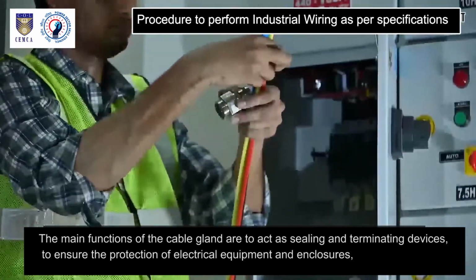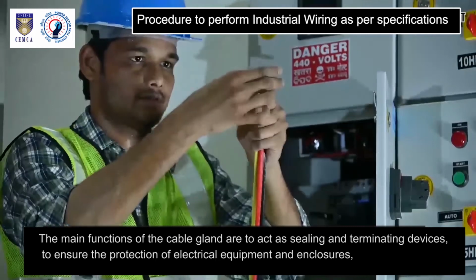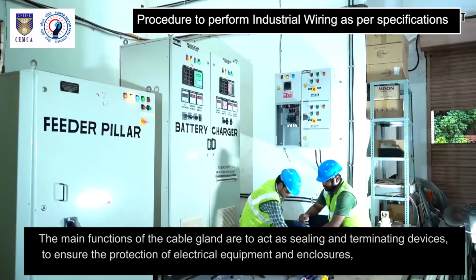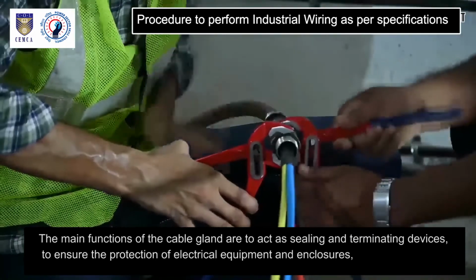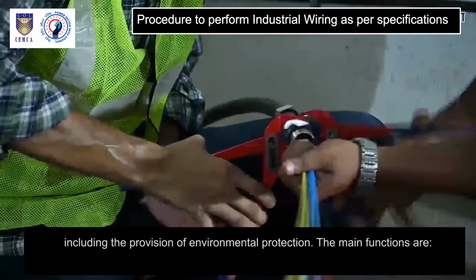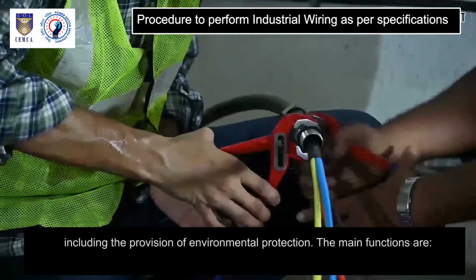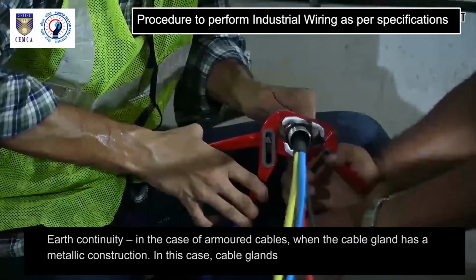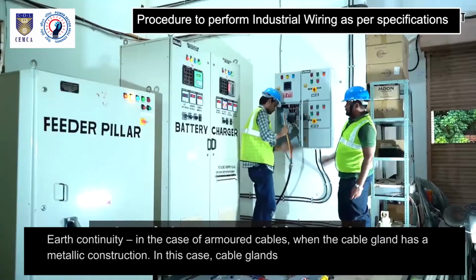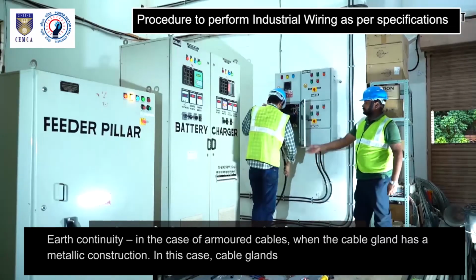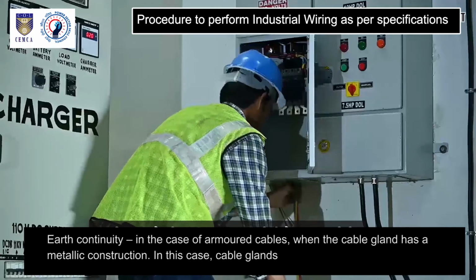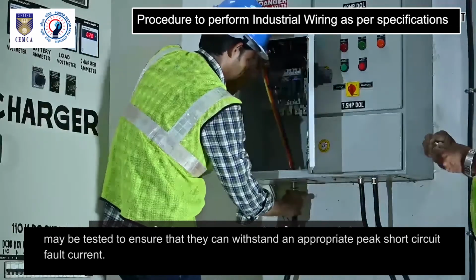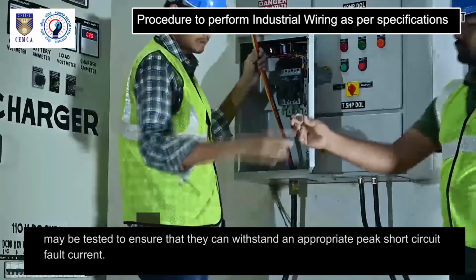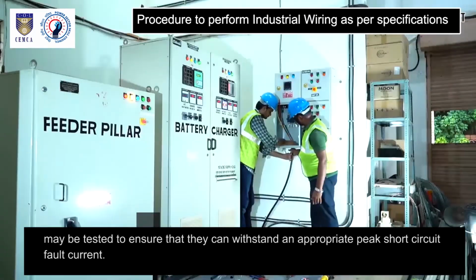The main functions of the cable gland are to act as sealing and terminating devices, to ensure the protection of electrical equipment and enclosures, including the provision of environmental protection. The main functions are earth continuity. In the case of armored cables, when the cable gland has a metallic construction, cable glands may be tested to ensure that they can withstand an appropriate peak short circuit fault current.